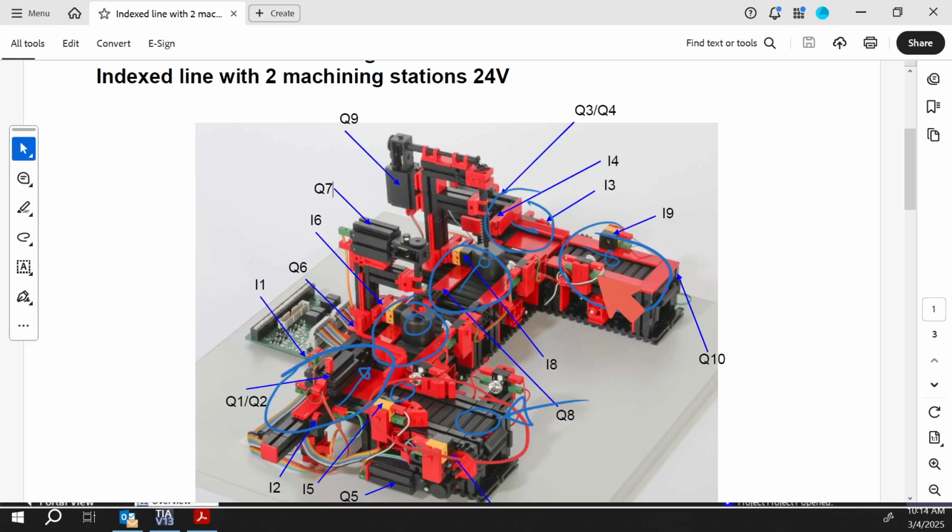You could write your code once and just say, here's the inputs for conveyor 1, section 1. Here's the inputs for conveyor 2, section 1. Here's 3, section 1. Here's 4, section 1. Here's 5, section 1. And that means when you find out there's a problem, like, oh, we should have used sensor B instead of C or whatever the case is, all you have to do is change your code in one location, and it updates your code everywhere. Now, sometimes that's a good thing, and sometimes that's not, because if they're running ever so slightly differently, you're like, oh, we need to add a sensor on this one because it runs slower.